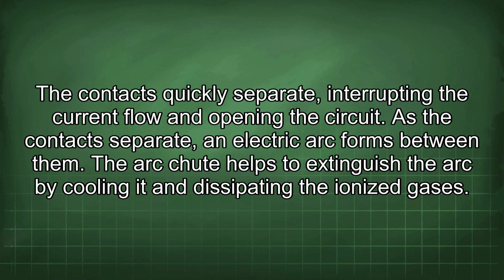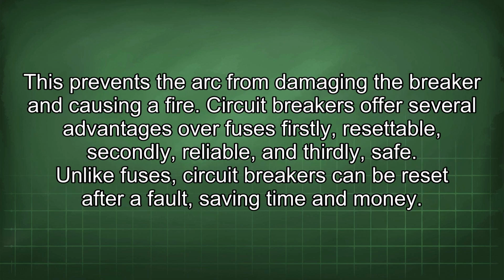As the contacts separate, an electric arc forms between them. The arc chute helps to extinguish the arc by cooling it and dissipating the ionized gases. This prevents the arc from damaging the breaker and causing a fire.